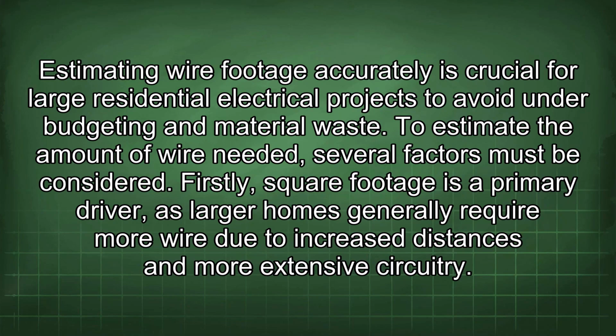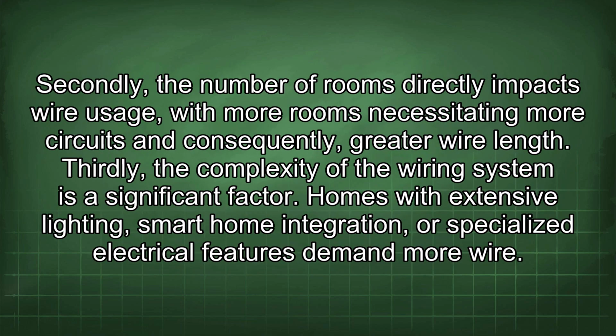Estimating wire footage accurately is crucial for large residential electrical projects to avoid under-budgeting and material waste. To estimate the amount of wire needed, several factors must be considered. Firstly, square footage is a primary driver, as larger homes generally require more wire due to increased distances and more extensive circuitry. Secondly, the number of rooms directly impacts wire usage, with more rooms necessitating more circuits and consequently greater wire length. Thirdly, the complexity of the wiring system is a significant factor.